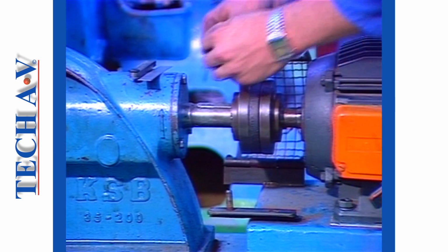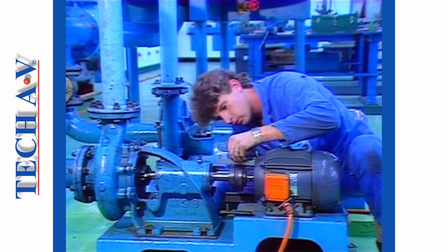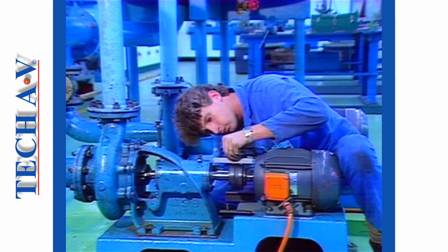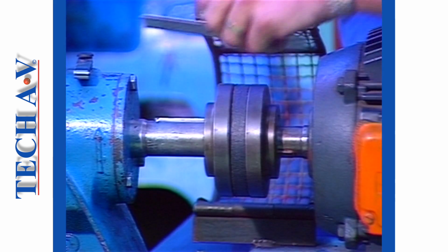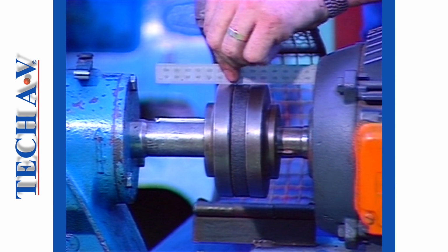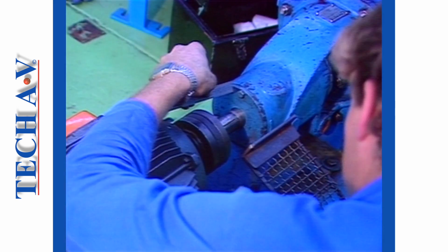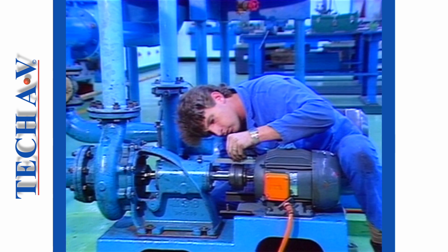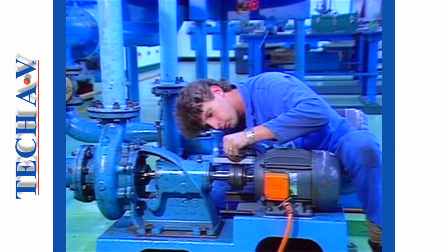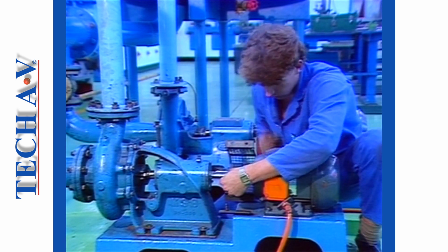A coupling may take many forms, the simplest being two half couplings keyed onto each shaft. The two halves are then carefully aligned. Correct coupling alignment is a critical factor in the task of pump installation and is the subject of a full training program. However, in essence, the pump fitter must ensure that both the pump and the drive unit are in perfect alignment to prevent severe mechanical damage.